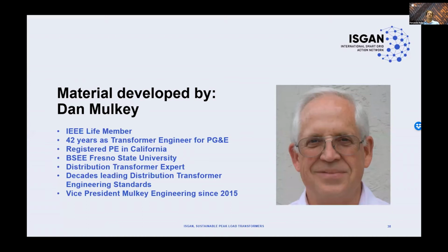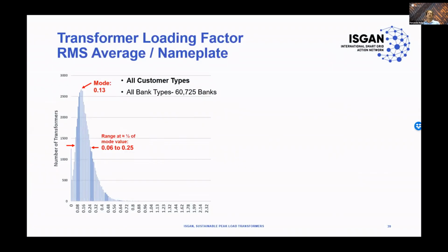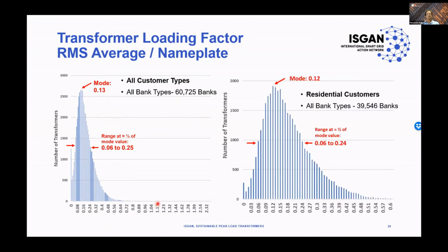So here we will present a survey carried out by Dan Mulkey, an IEEE Life member with 42 years of experience. Basically, the analysis he carried out is as follows. He measured the behavior of more than 60,000 transformers on the East Coast of the US, in 15-minute data points, so a huge amount of data points over more than 1 year. And then he prepared this root mean square average over nameplate capacity. So basically these points give us the average loading.